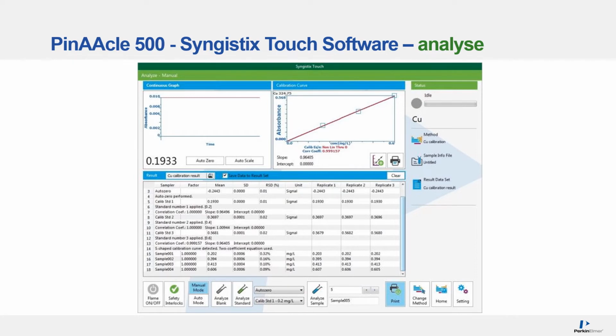on the far right-hand side in the status panel, you can see that there is a method listed, but there's also a sample information file listed. If you were to click on that, it would open up your sample information file, and you would be able to make a pre-list of all the samples you intend to run so that you don't have to type them out manually as you're running them.